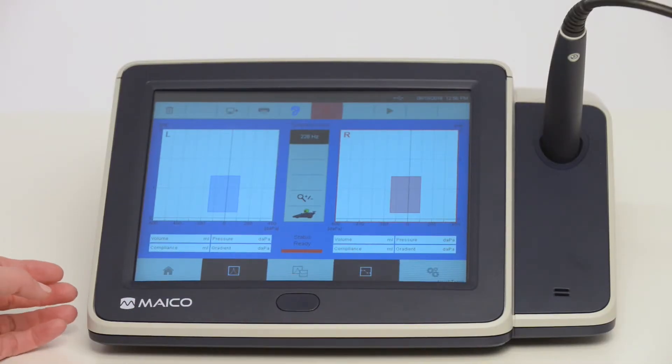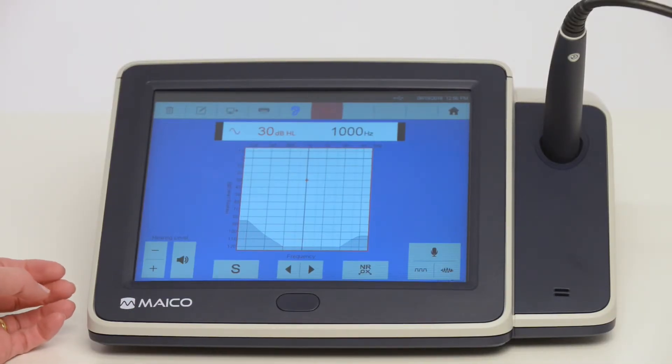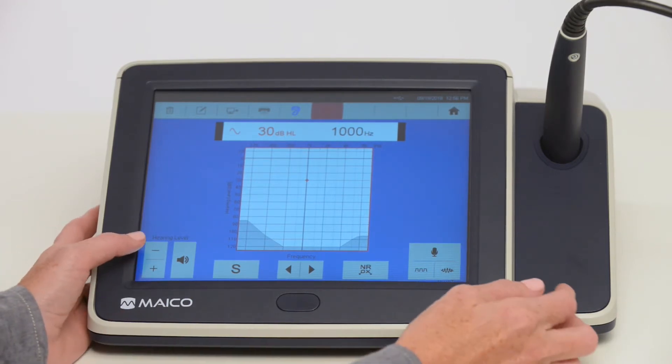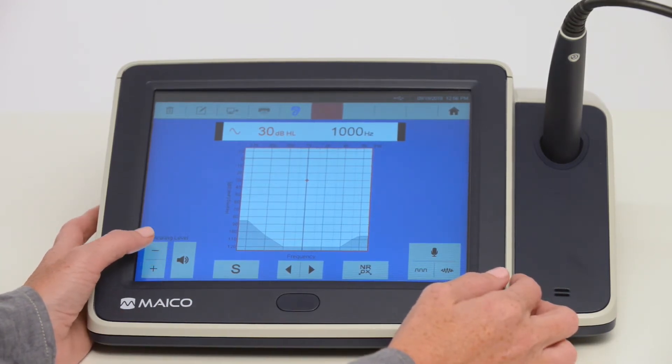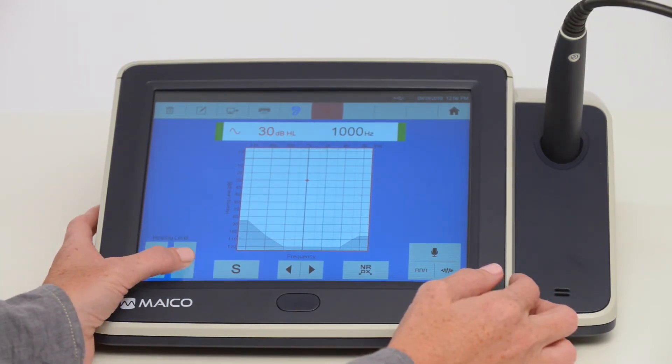Using the touch screen, select audiometry from the bottom row of icons. Select right or left ear. Selection of test frequency is with the frequency arrow buttons. Select the volume with the hearing level arrows. Touch the speaker button to present the tone.